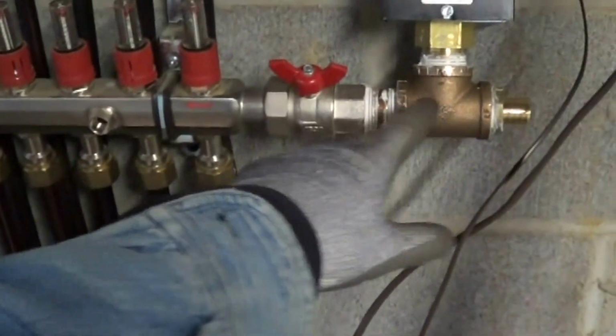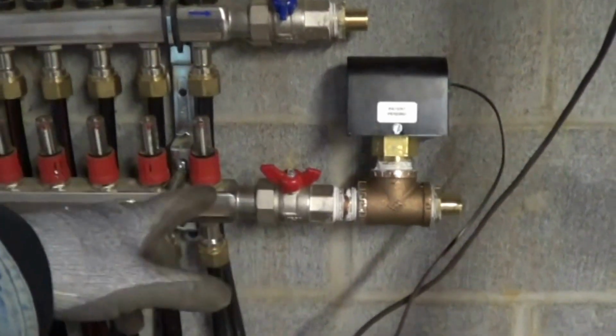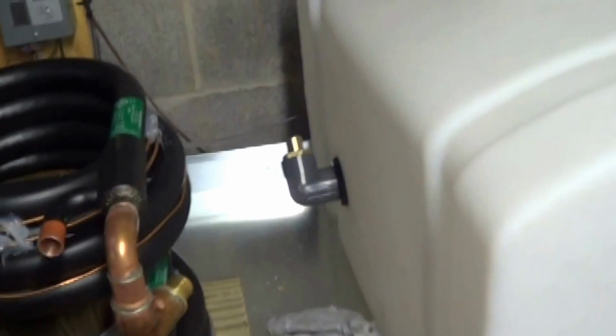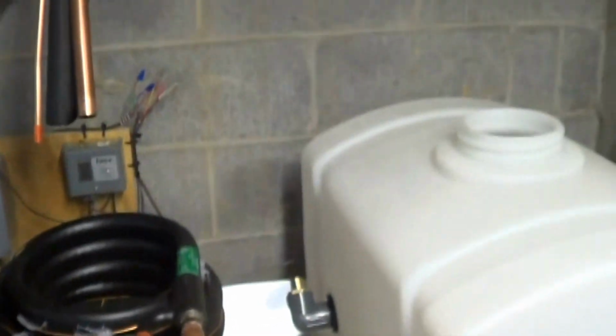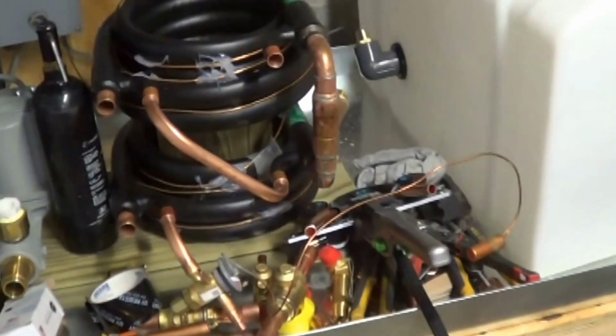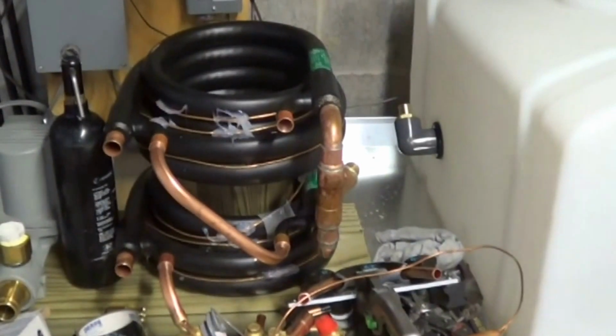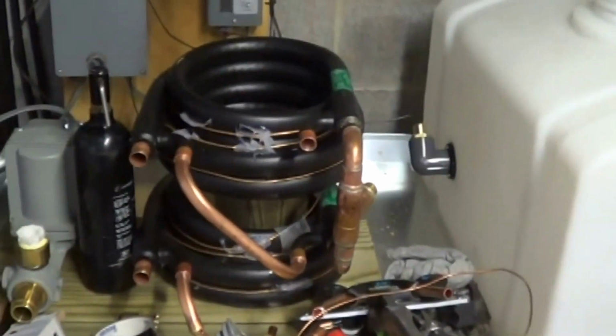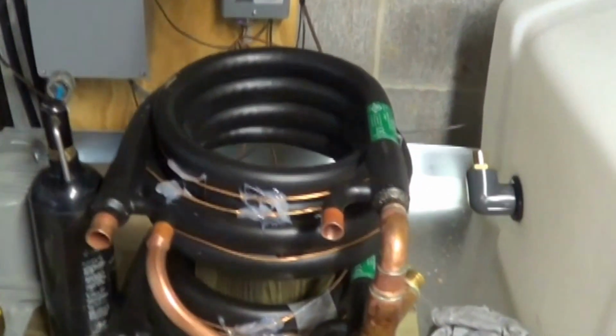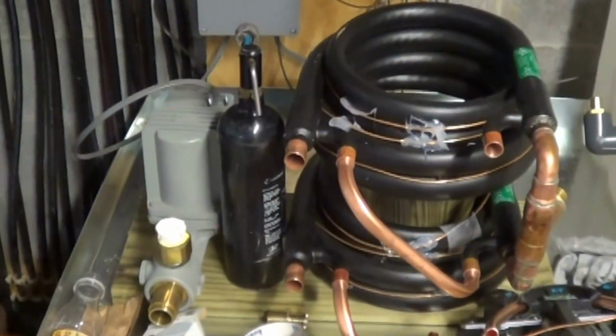Then the heat exchanger goes out to our supply manifold, we got our safety switch there, flow switch, and then the return, it's gonna dump back into the tank. And I raised this up a little bit, so if the tank's ever low, you start hearing it splash in there, and then you know you gotta juice the loop with some water, which is basically just pour in a bucket. And then we got plenty of room for expansion. And I checked on radiant floor cooling. It doesn't really work because your floor ends up just sweating, and you know, who wants that in the summertime? So that's why we're gonna do air for the cooling.